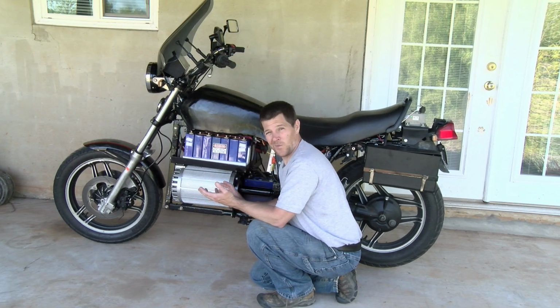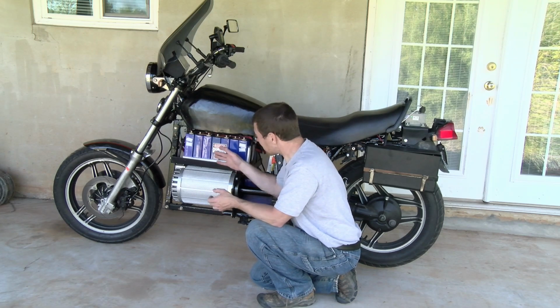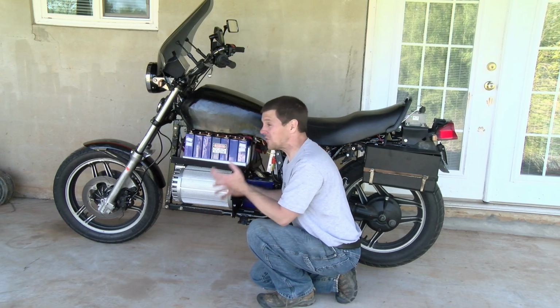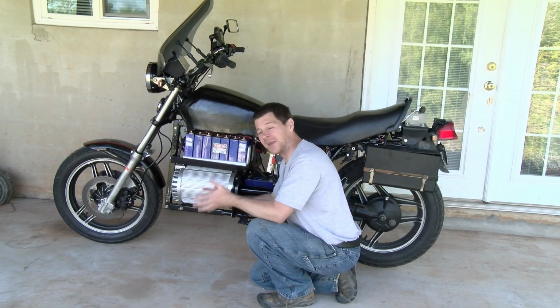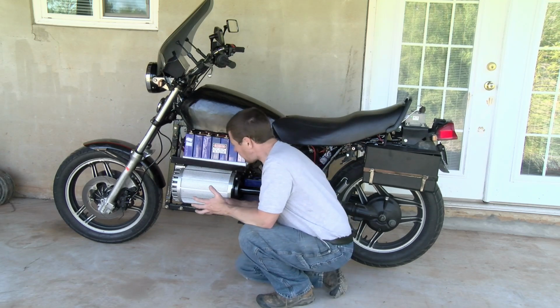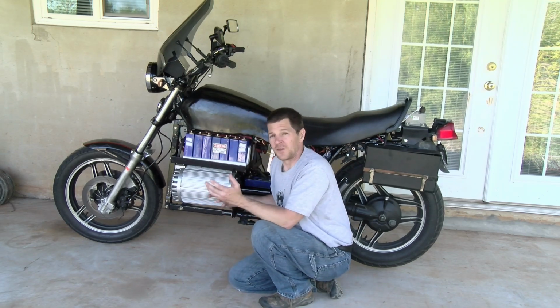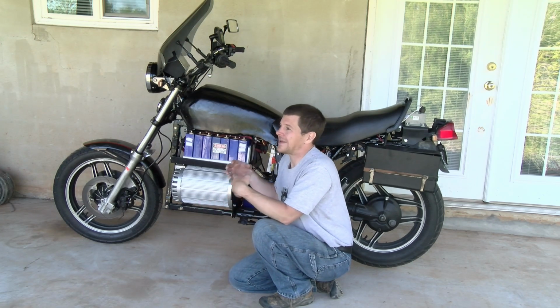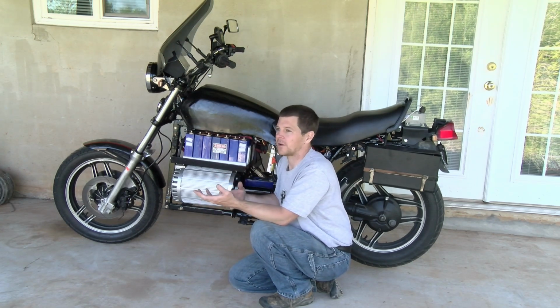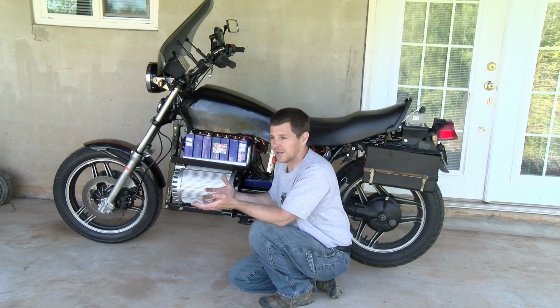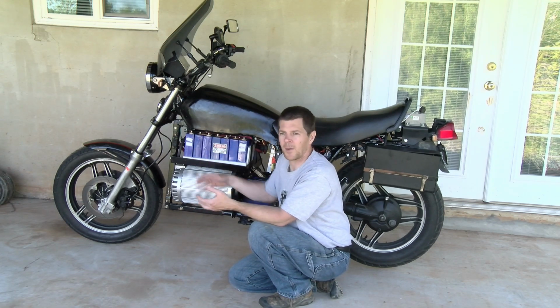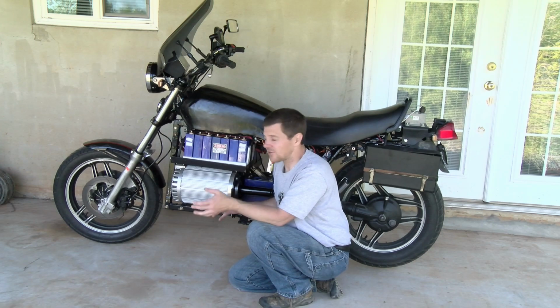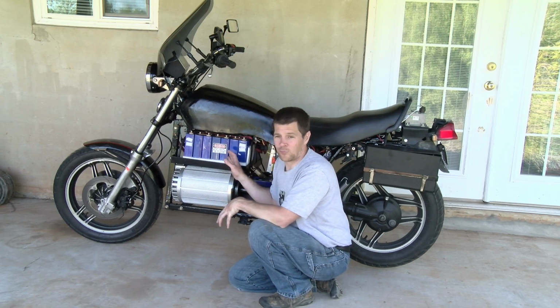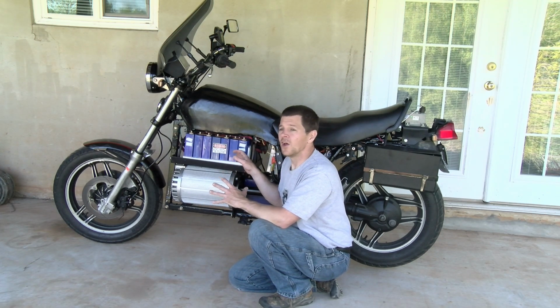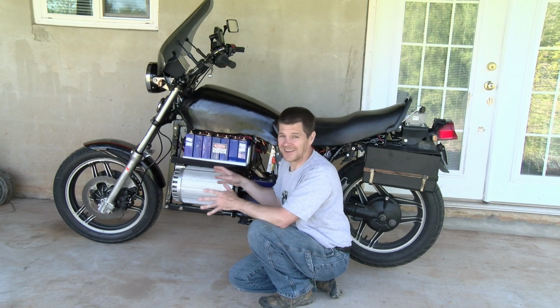So why would I do that? Well, the great thing about lithium phosphate is you can absolutely beat the snot out of them. Most batteries are rated with what's called a C rating, meaning how many times in an hour the battery could discharge its full capacity. So 1C on a 120 amp hour battery would be 120 amps. These are rated at 3C, so 360 amps apiece.